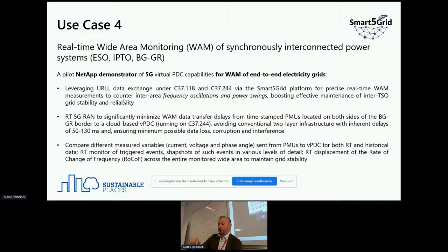The fourth use case, which is most relevant from a transmission system operator point of view, is how we can manage interconnected power grids, in this case between Greece and Bulgaria, using a 400 kV interconnection. We use data from devices installed in both substations across the border, called PMUs, or phasor measurement units, sending data via 5G infrastructure to a virtual phasor data concentrator, which feeds the use case specific network application, providing faster and more flexible monitoring compared to legacy systems.